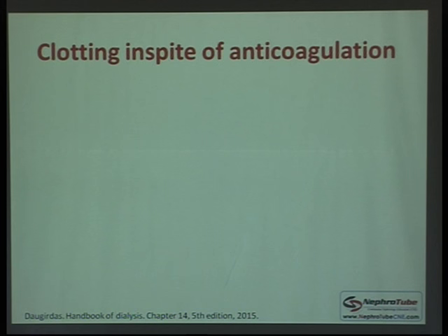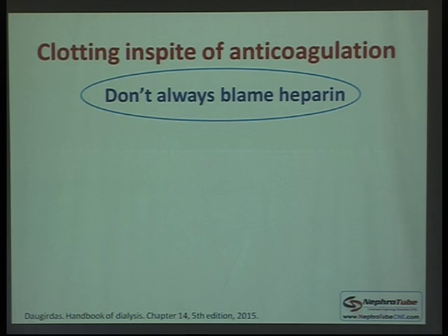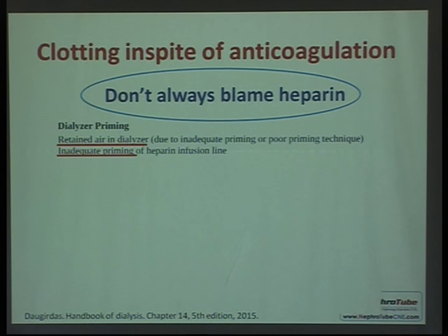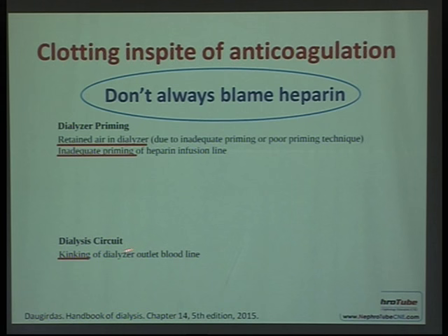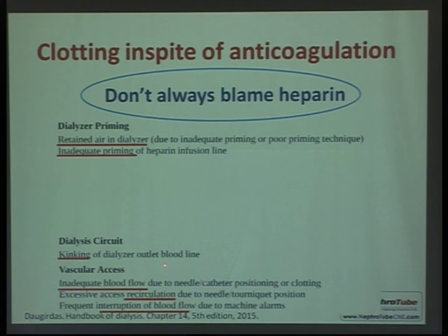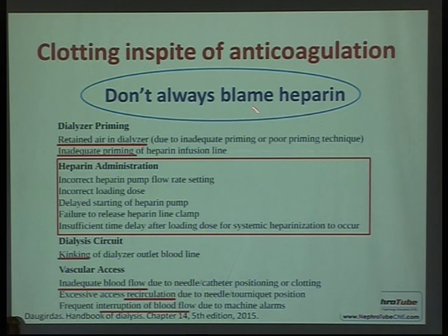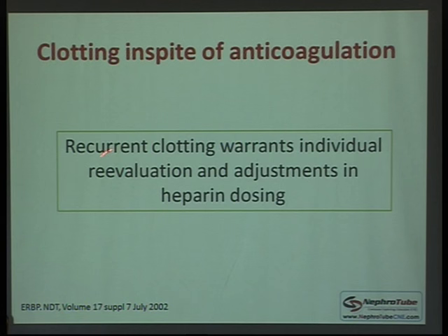If clotting occurs despite anticoagulation, don't always blame heparin. Other causes include inadequate priming with air retention in the circuit, kinked dialysis circuits, vascular access problems such as inadequate blood flow due to stenosis, recirculation, or interruption of blood flow due to machine alarms, or a problem with heparin administration or dosage. Especially if there is recurrent extracorporeal clotting and you are sure adequate heparin is being given, re-evaluate and look for other causes, though recurrent clotting does warrant re-evaluating and adjusting the heparin dose.